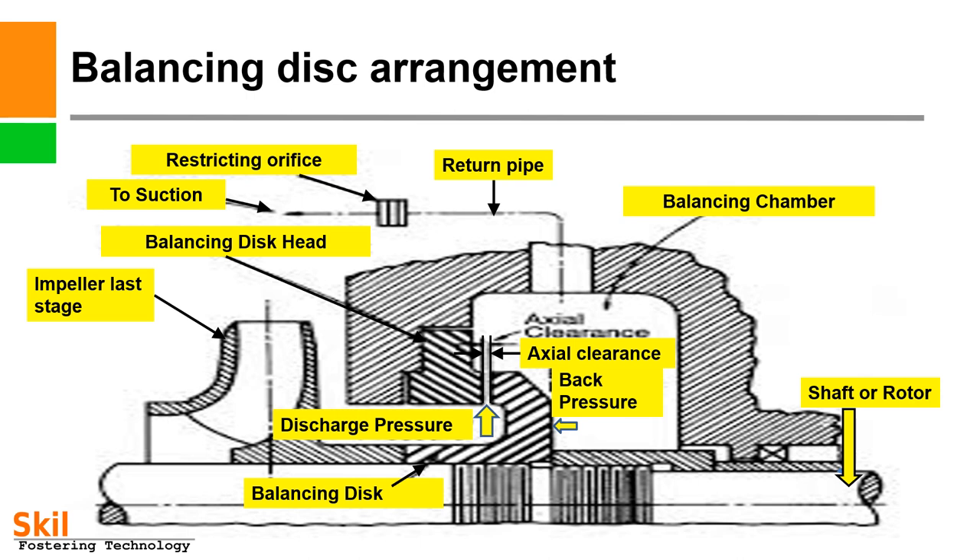Balancing disc arrangement. A picture of a balancing disc arrangement of a multi-stage pump is shown. Here you can see the last stage impeller. This is a balancing disc which is fixed on the shaft. This is a balancing head or counter-balance device which is fixed in the casing as a stationary part. This is a return pipe going to suction through a restricting orifice; a cooler may also be provided in this return pipe. This is the balance chamber, which maintains pressure to counter axial thrust through back pressure on the balancing disc.